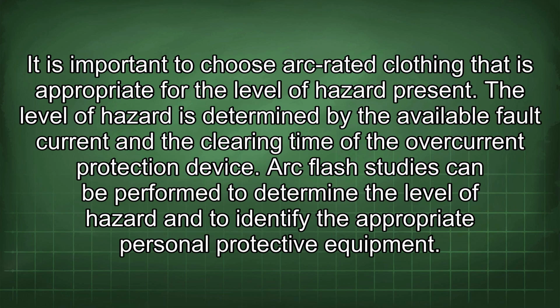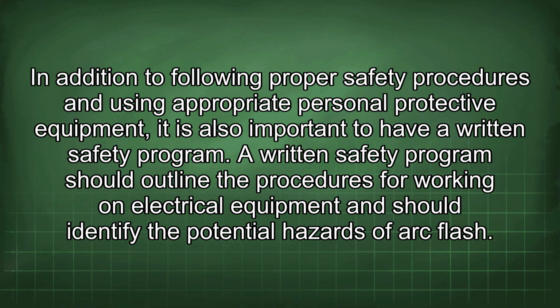Arc-rated clothing is designed to protect against the heat and flames of an arc flash. It is important to choose arc-rated clothing that is appropriate for the level of hazard present. The level of hazard is determined by the available fault current and the clearing time of the overcurrent protection device. Arc flash studies can be performed to determine the level of hazard and to identify the appropriate personal protective equipment.